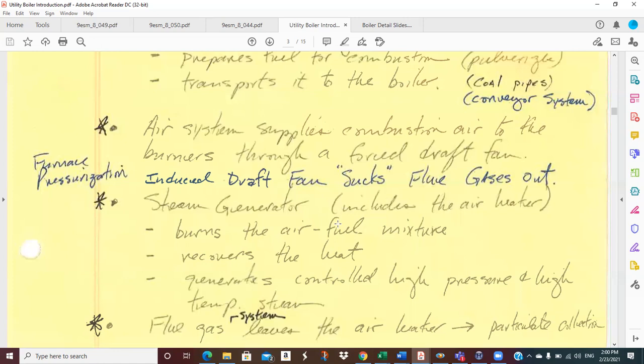Well, the other set of units has a much more intelligent design, with the ID fans downstream of the precipitator. So it's a clean gas. Now, it may have pollutants, like SO2 or NOx, but it doesn't have particulates that eat holes in the fans. And that has been a major maintenance bugaboo for the last 50 years. Kingston knows more about gluing ceramic tiles on centrifugal fans than just about anybody in the world, because they've been doing it for 50 years. So instead of rebuilding the fan and the wheel every year, they can rebuild it every 2 years. It's still a pain in the rear.